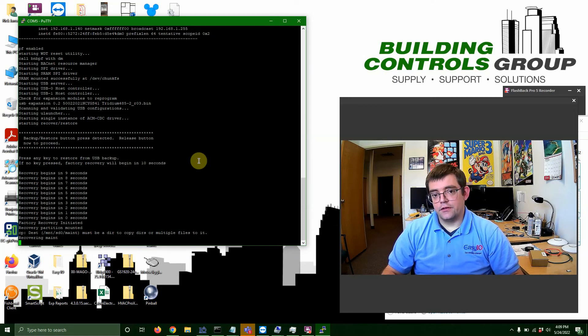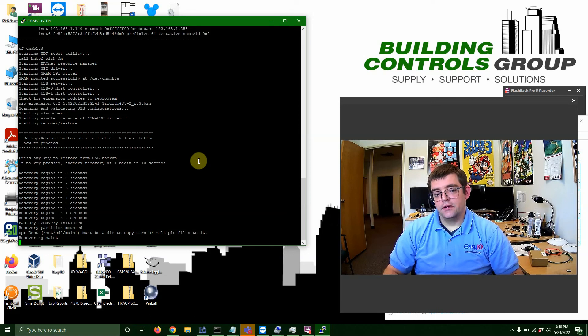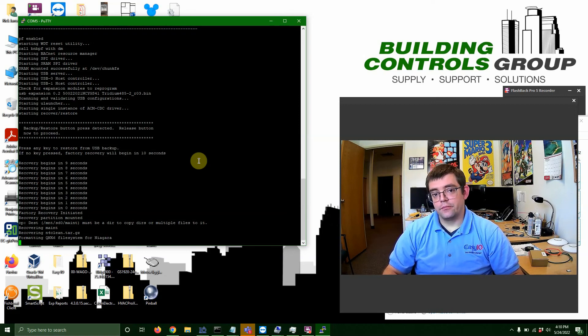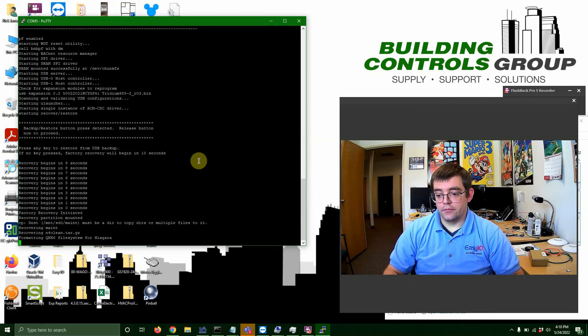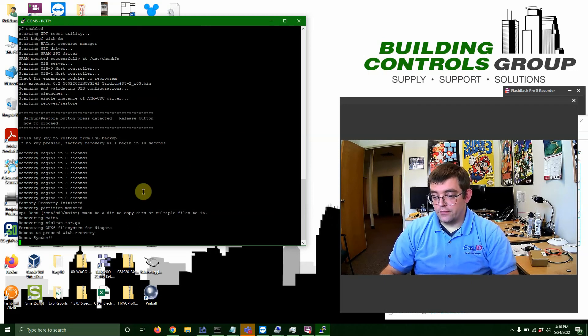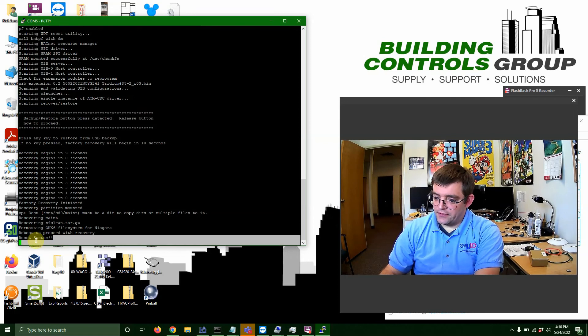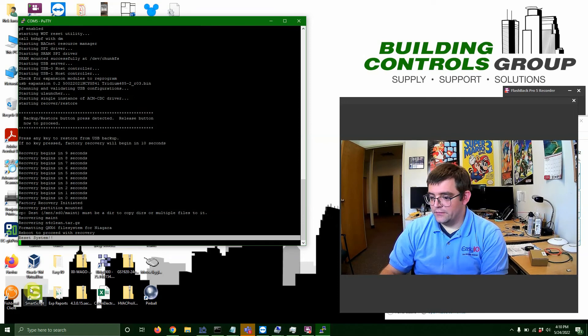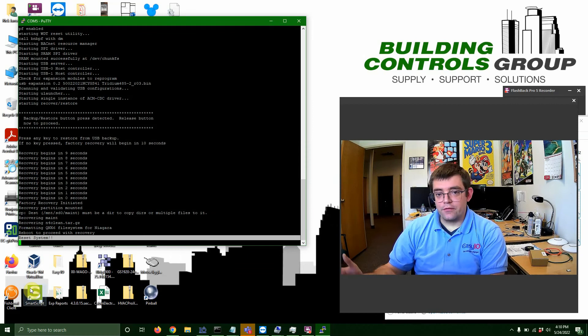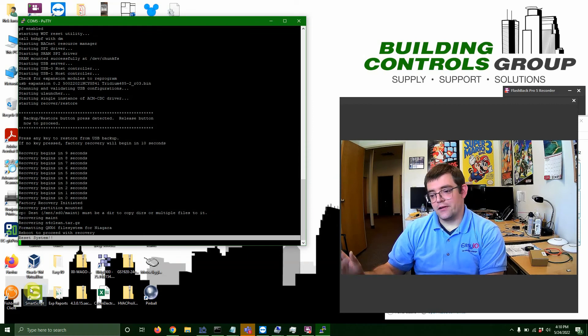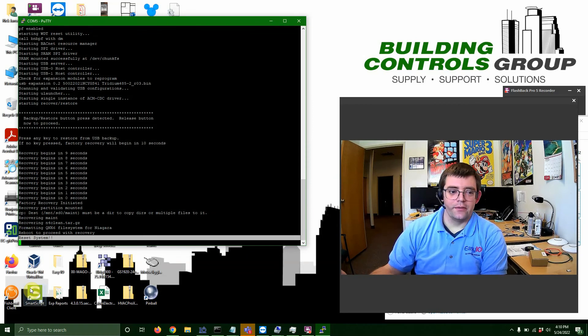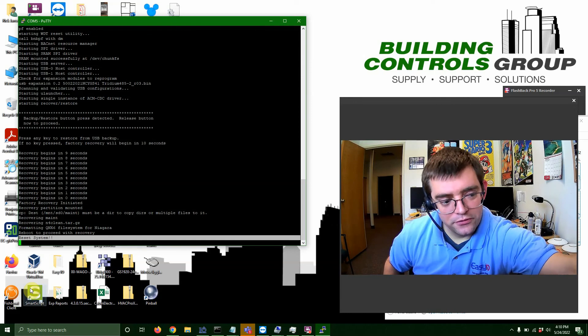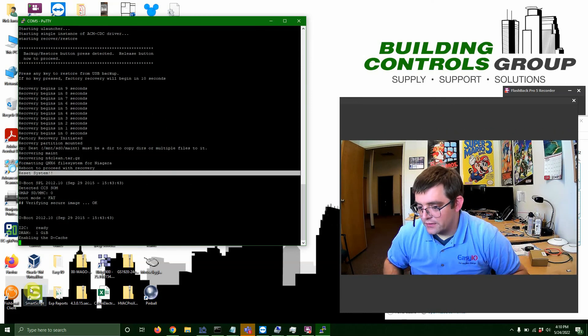So be aware that if you need to back that stuff up if you can, you know, most of the time we're resetting these Jace is because something catastrophic has happened to the point to where we can't get in through Workbench normally. And that's what's happened here. So one thing I always get messed up on, see where it says reset system? I always, for whatever reason, expect this to just magically happen on its own. What this is actually telling you to do is unplug the Jace and plug it back in. So that's what we're going to do right now.